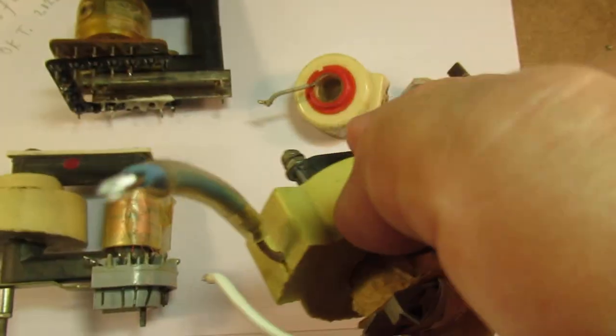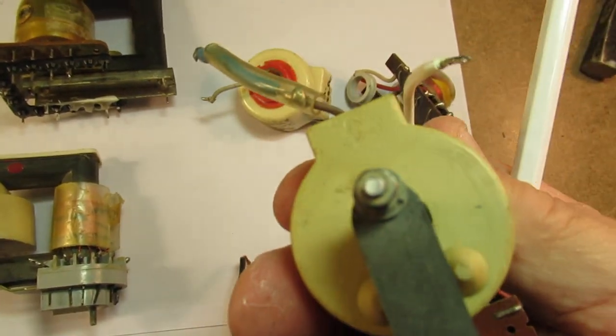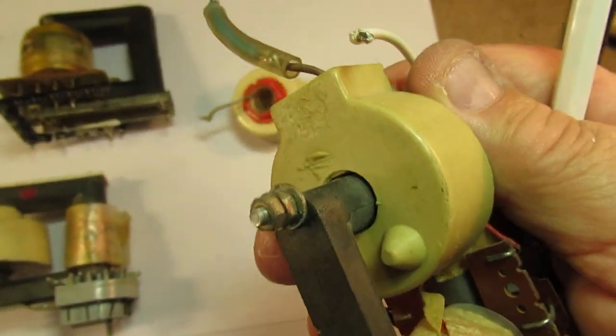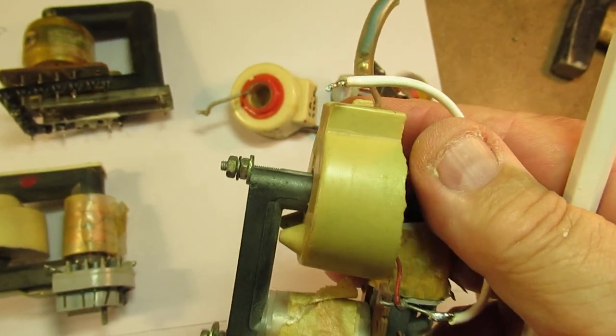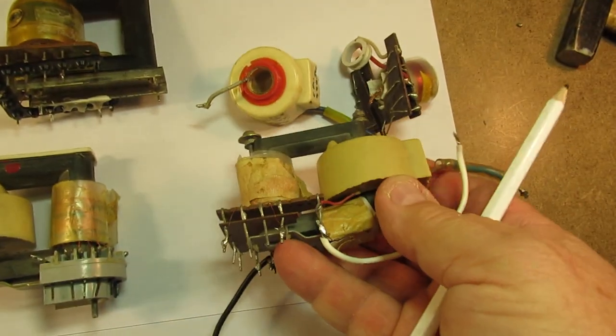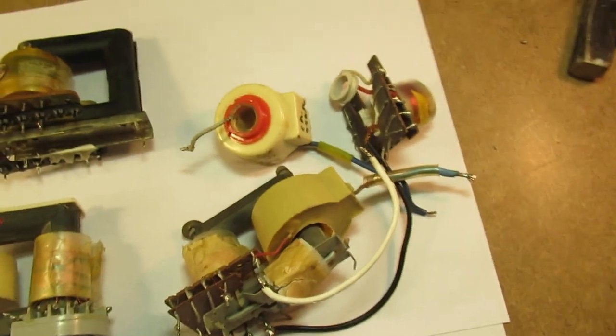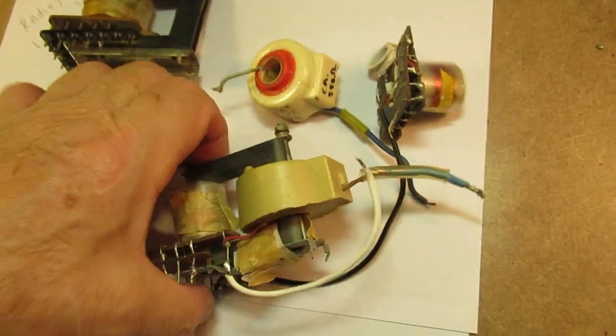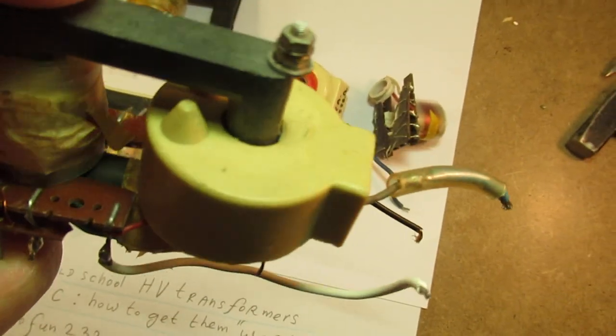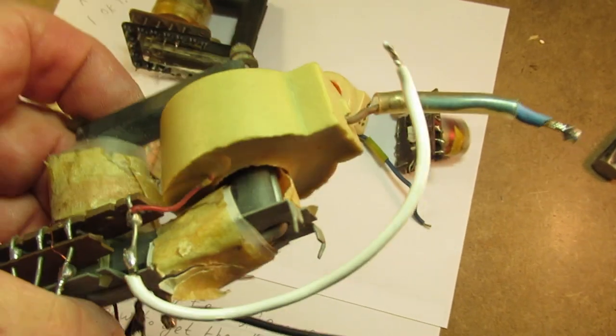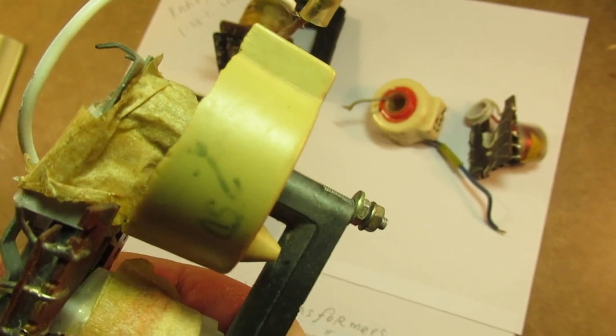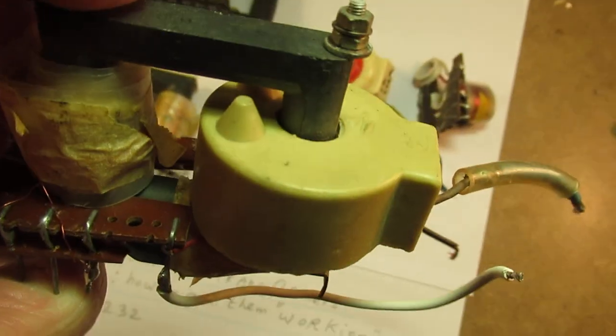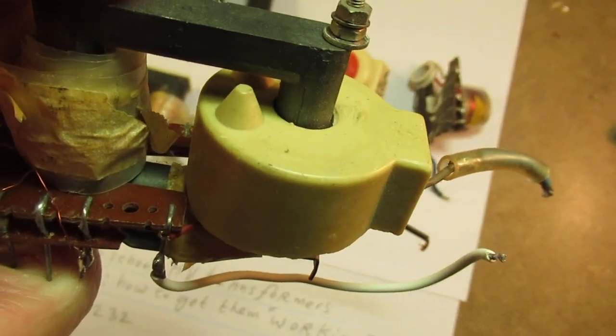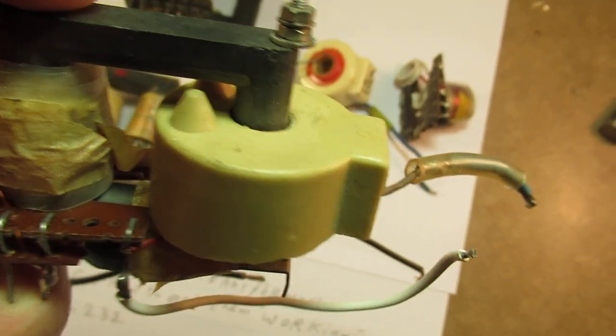It is immersed in a kind of epoxy resin, and the reason is, of course, that it has to endure the high voltages, so no sparks may occur in the windings of that high voltage secondary. So it's immersed in a very good quality resin.